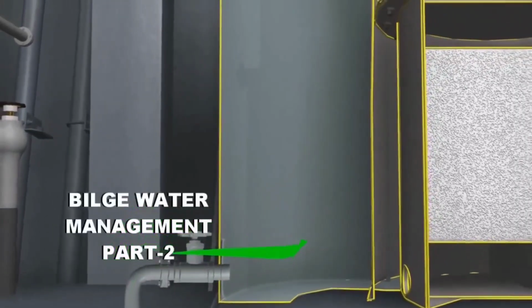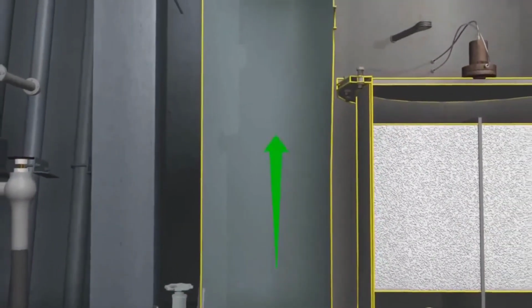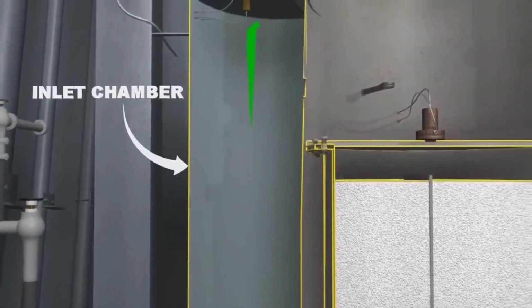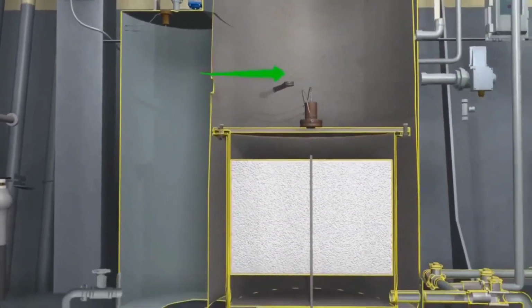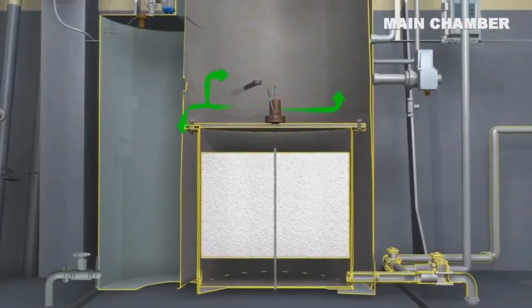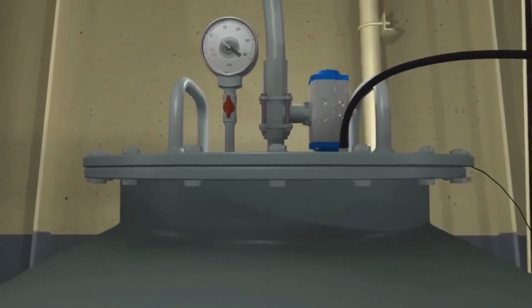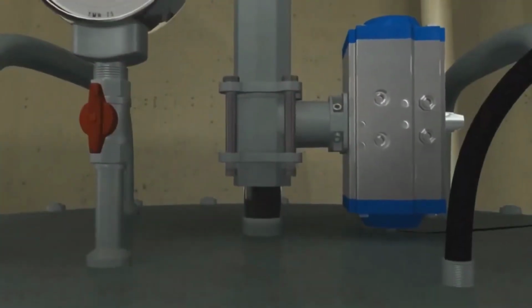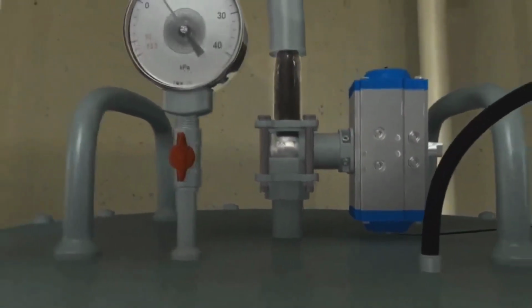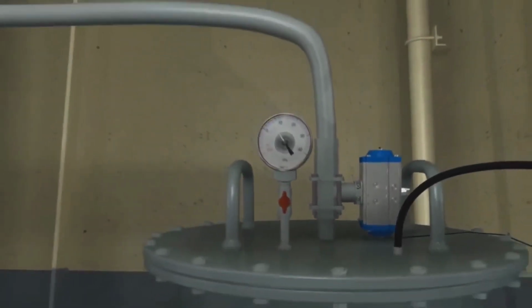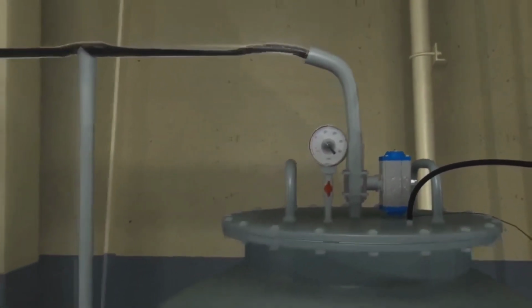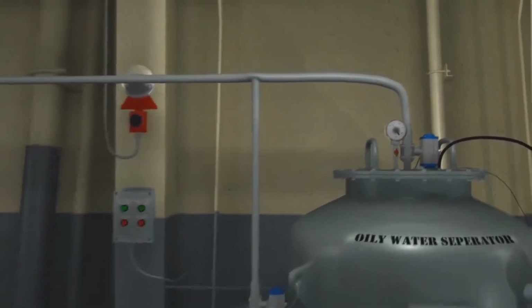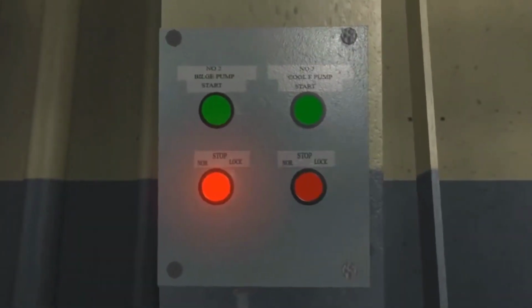First, let us trace the path the oily water takes from the bilge pump discharge to the overboard valve. Once the oil is detected at the sensor here, the following operations are executed simultaneously. 1. The pneumatic valve on top of the main chamber is automatically operated, which directs the oil to the separated bilge oil tank. 2. The bilge pump is automatically stopped.